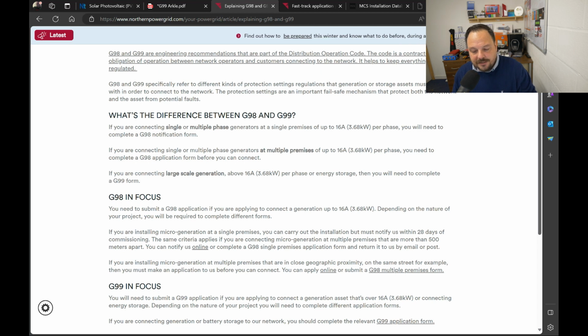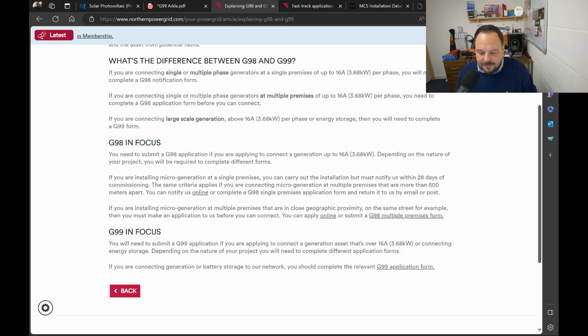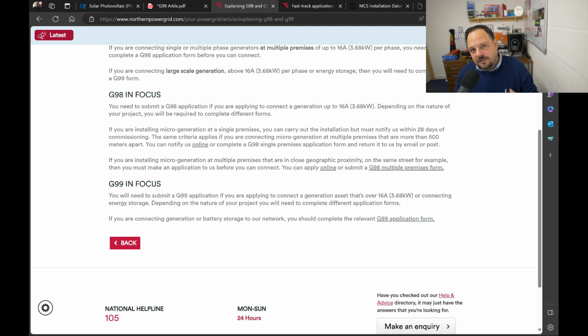For single or multi-phase generators at a single premises of up to 16 amps, so 3.68 kilowatt per phase, you complete a G98. With a G98, you can do your installation first and then notify them within 28 days that you've connected that equipment onto their service provision. Whereas with a G99, you have to actually apply to them first and ask for permission to connect. Those are the key differences there, and if you're over 16 amps, you need to be doing a G99.